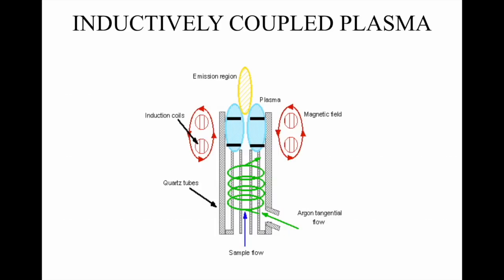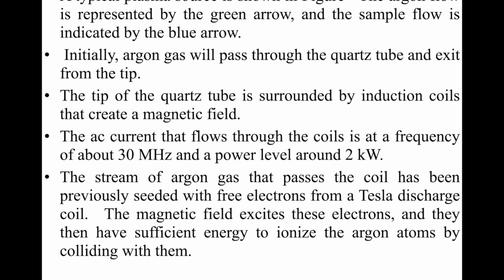Now coming to the inductively coupled plasma. A typical plasma source is shown in the figure. The argon flow is represented by the green arrow and the sample flow is indicated by the blue arrow. Initially, argon gas passes through the quartz tube and exits from the tip. The tip of the quartz tube is surrounded by an induction coil that creates a magnetic field. The AC current flowing through the coils is at a frequency of about 30 megahertz and a power level of around 2 kW. The stream of argon gas passing the coil has been previously seeded with free electrons from a Tesla discharge coil. The magnetic field excites these electrons, giving them sufficient energy to ionize the argon atoms by colliding with them.